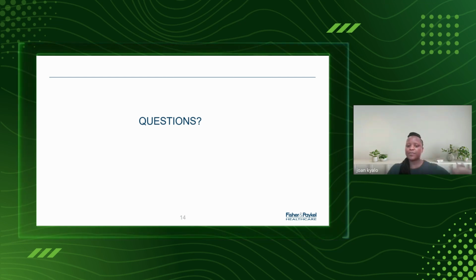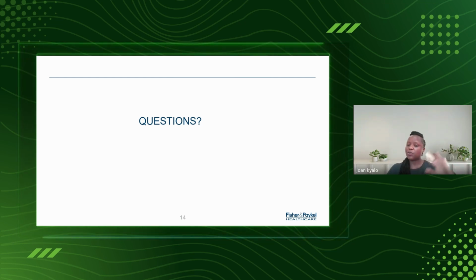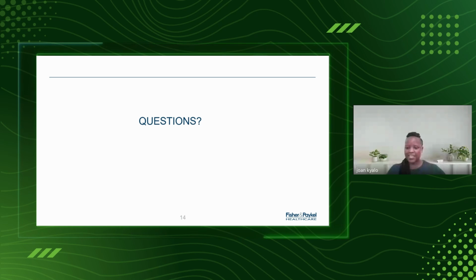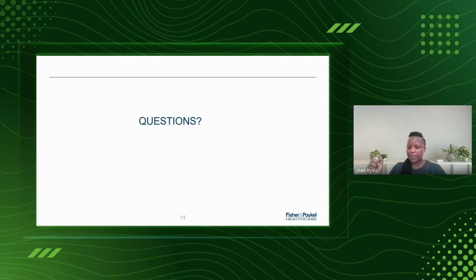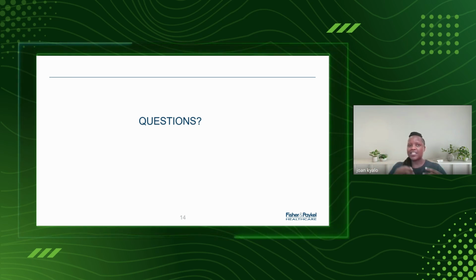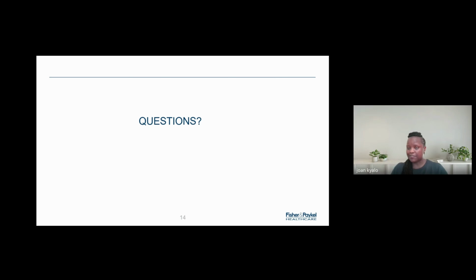The part of humidity I've talked about is all passive humidity, so there is no heating. It's basically the gas interacting with water and picking up some humidity. The maximum you can pick up is like 20 milligrams of water, and we said optimum humidity is 44 milligrams. That 20 depends on a lot of things: the oxygen you have, the sort of setup, and also the brand itself.